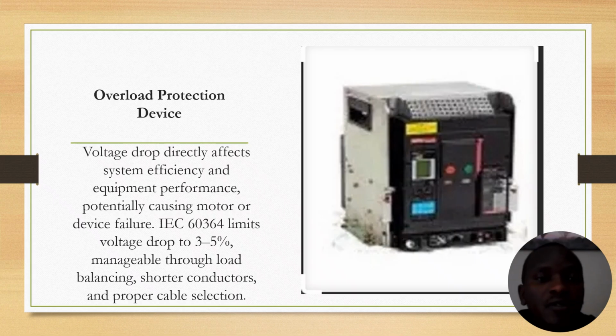Voltage drop directly affects system efficiency and equipment performance, potentially causing motor or device failure. IEC 60364 limits voltage drop to 3 to 5%, manageable through load balancing, shorter conductors, and proper cable selection. So it is important for you to select the proper cable, whereby the conductor must be within 3 to 5%, manageable for the load.